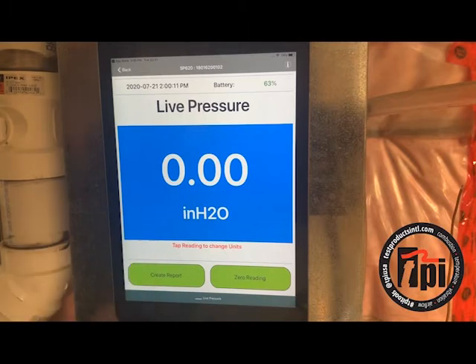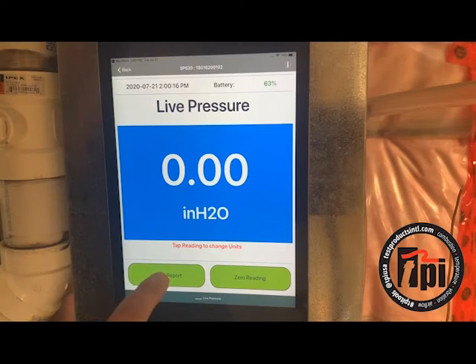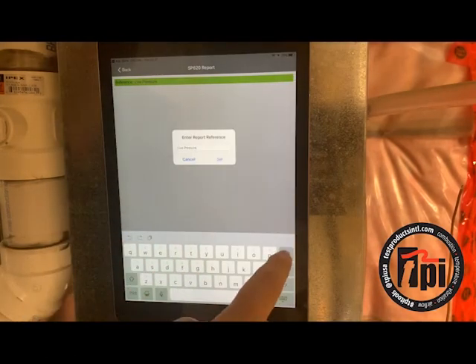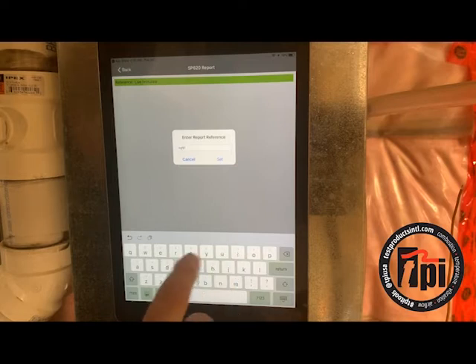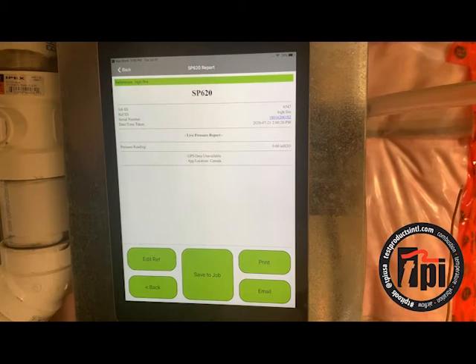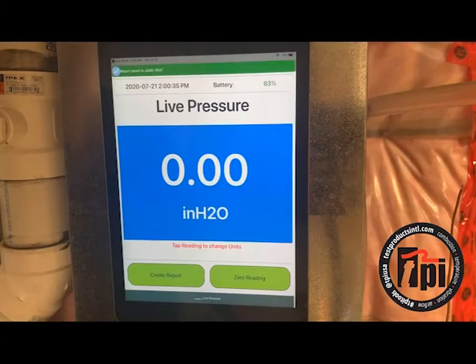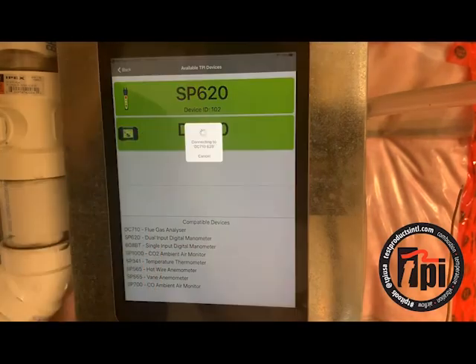The next thing we're going to do is probably be my high fire reading. Wait until it gets up to the pressure required by the manufacturer of the equipment, then create report. I'm going to call this 'high fire.' There it is — saved to job. So now I've got my low fire and my high fire saved in there. And the next instrument that I've got turned on is my DC710 combustion analyzer.